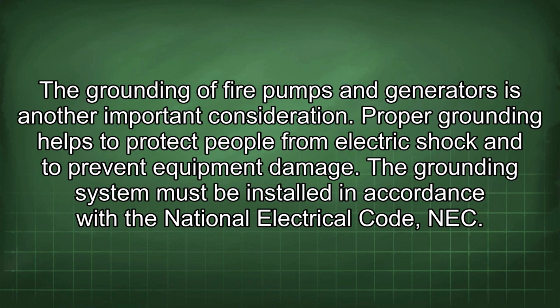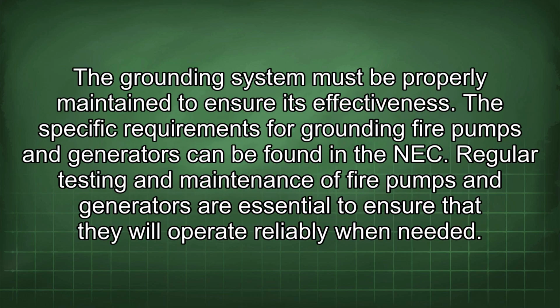The grounding of fire pumps and generators is another important consideration. Proper grounding helps to protect people from electric shock and to prevent equipment damage. The grounding system must be installed in accordance with the National Electrical Code (NEC). The grounding system must be properly maintained to ensure its effectiveness. The specific requirements for grounding fire pumps and generators can be found in the NEC.